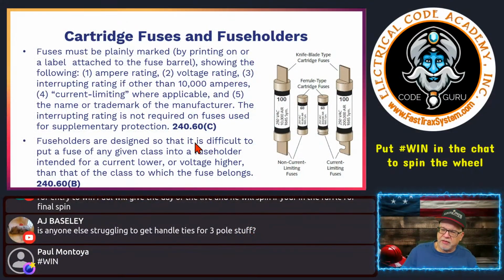Fuse holders are designed so that it is difficult to put a fuse of any given class into a fuse holder intended for a current lower or voltage higher than that of the class to which the fuse belongs, 240.60(B). This is also one of those things you heard me talk about the other day about a 601. A 601 is designed to go in, let's say, an 800 amp frame, but it's a 600, and it is designed so it can fit in there, even though it's only 601. But it's designed so it fits into a larger frame. So a 601 is a standard. You saw us in 240.6(A) the other day that a 601 is a standard size, low-hanging fruit on an exam when they ask you different sizes on what is considered a standard, for example in a fuse.